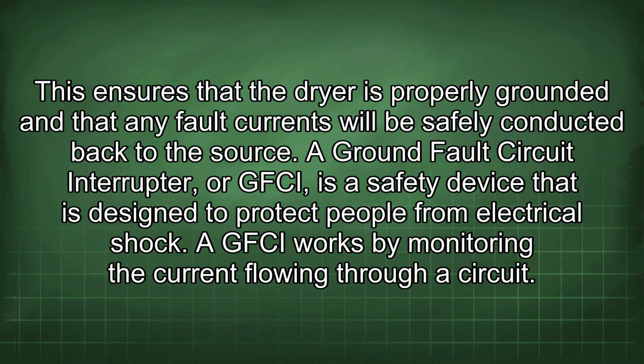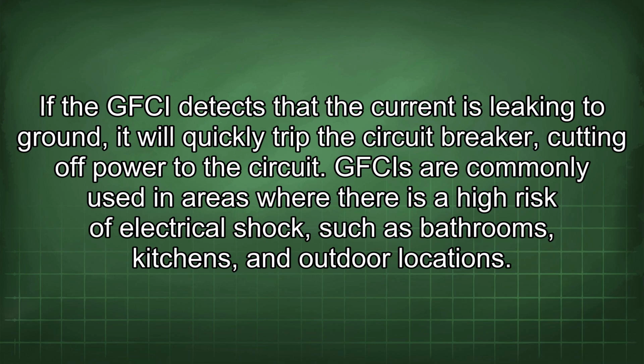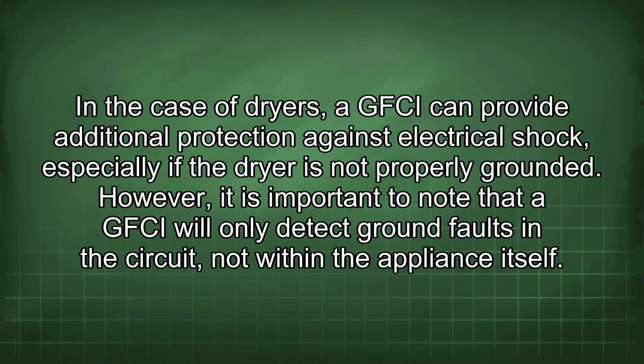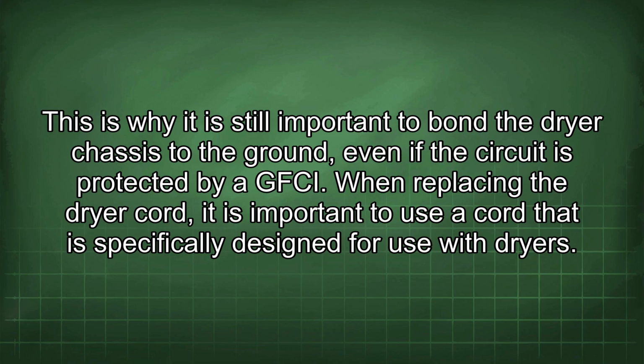A ground fault circuit interrupter, or GFCI, is a safety device that is designed to protect people from electrical shock. A GFCI works by monitoring the current flowing through a circuit. If the GFCI detects that the current is leaking to ground, it will quickly trip the circuit breaker, cutting off power to the circuit. GFCIs are commonly used in areas where there is a high risk of electrical shock, such as bathrooms, kitchens, and outdoor locations. In the case of dryers, a GFCI can provide additional protection against electrical shock, especially if the dryer is not properly grounded. However, it is important to note that a GFCI will only detect ground faults in the circuit, not within the appliance itself. This is why it is still important to bond the dryer chassis to the ground, even if the circuit is protected by a GFCI.